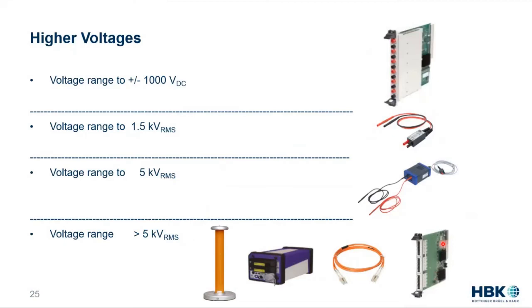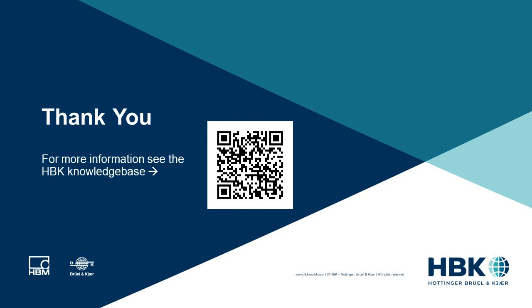Now, some of these lightning strike, corona discharge events are transient. And I told you that we have this card that's 2 megasamples per second, but for some of these transient events, that might not be enough. These cards can actually go up to 100 megasamples per second, so you can really start to understand that. We have a strong history in switchgear testing, and this is a big benefit for people going to high voltages or looking at voltage transients. So we have some really cool options in the high voltage world. We take safety extremely seriously, but also high accuracy measurement.